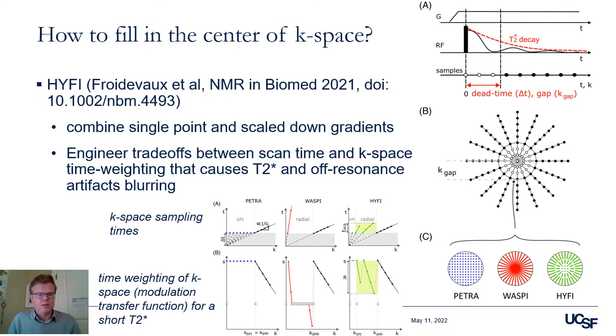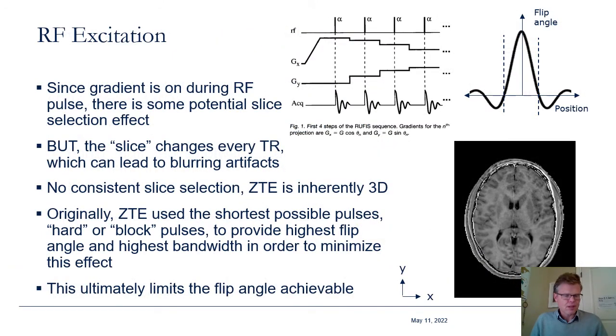Another exciting approach combines the best of PETRA's single point imaging and WASPI's scaled-down gradient approach into a technique called HYFI, where we can engineer the trade-offs between scan time and k-space time weighting — the modulation transfer function — that can lead to T2* and off-resonance blurring. PETRA gives consistently high signal for short times, while the radial acquisition in WASPI can lead to signal decay over the center of k-space, whereas HYFI can do a mixture of both.